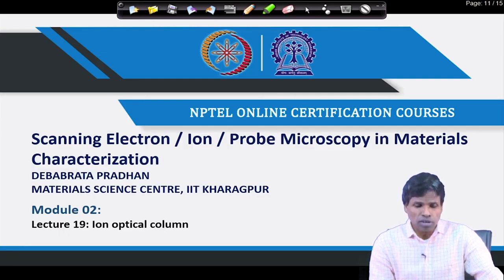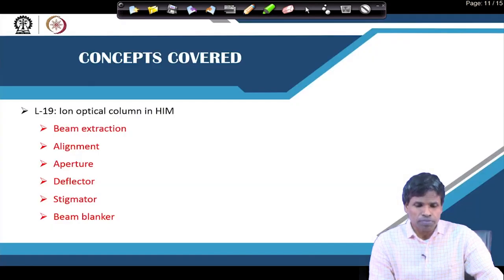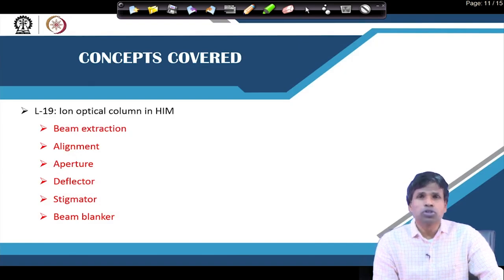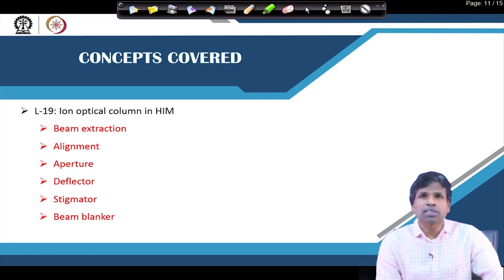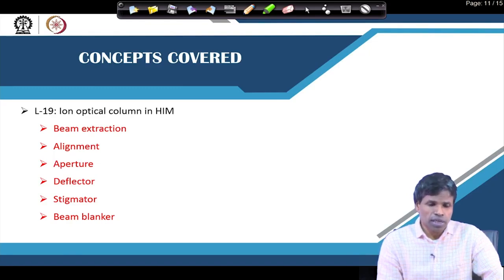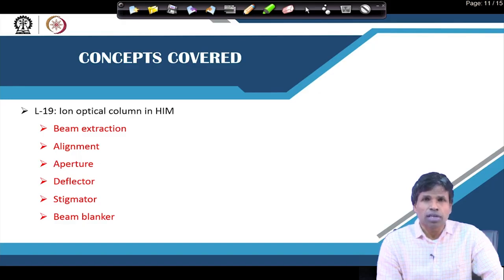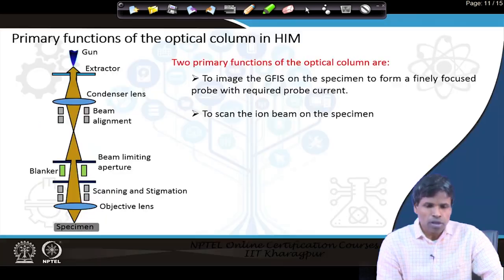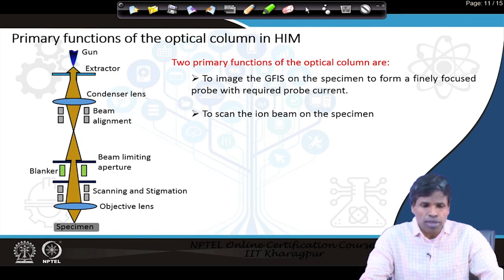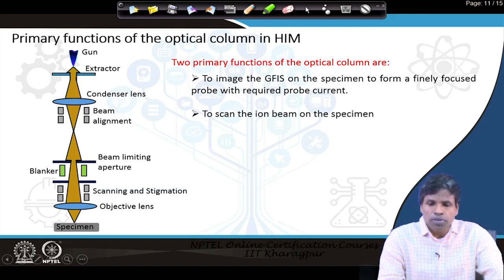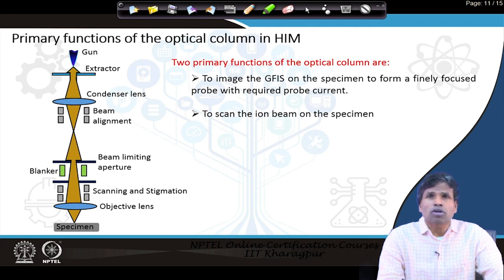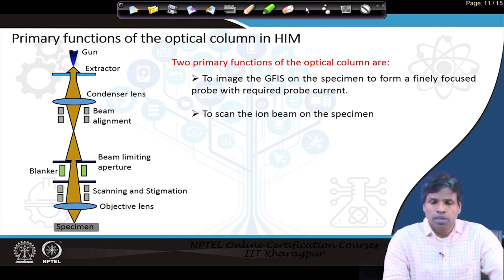Today we will see the ion optical column and how different parts are used in the ion optical column for aligning the beam and to bring the ion beam onto the specimen. In that regard, today we will be discussing beam extraction — how the ion beams are extracted from the source — then how it is aligned, the role of aperture, deflector, stigmator, and beam blanker. These are the parts that are present in the column of a helium ion microscope. The function of the column is to make a fine spot of ion on the specimen and also to scan the ion beam on the specimen.